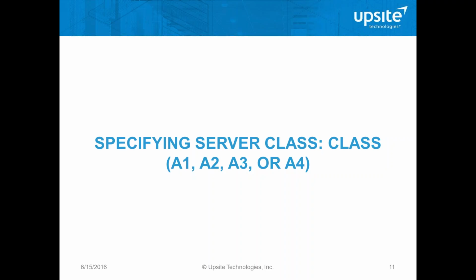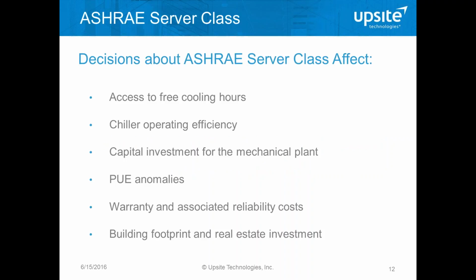Now, one thing to consider here is that historical differentiation between blade servers and pizza box servers is breaking down a little bit as some manufacturers are producing more efficient 2 and 3 unit servers. So your shopping for these servers should include delta T or CFM per kilowatt as some of your criteria. Also, when we're specifying servers, we're going to be specifying Class A1, Class A2, Class A3, or Class A4 servers. This becomes a little bit more complicated because you're very unlikely to find those labels on the boxes or on the nameplates or on the user documentation for those servers. So we're going to need to look at some other ways of identifying those.